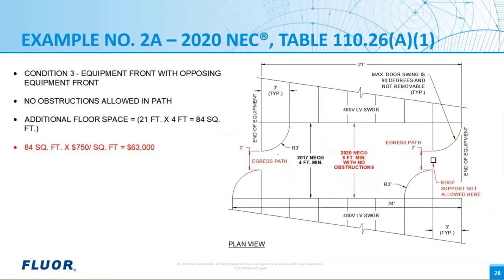From an economic standpoint, if we increase the working space from 4 feet to 8 feet for this 21-foot long piece of equipment at $750 per square foot, we're looking at an increased cost of $63,000 just for more floor space between the equipment, considering nothing else.